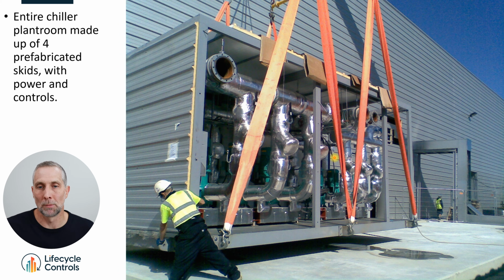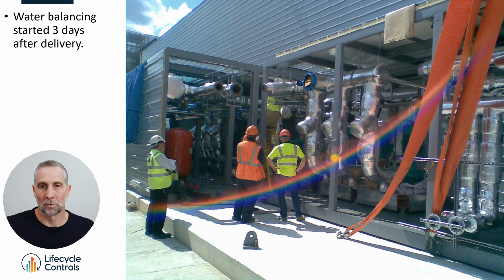This was a chiller plant room that was broken up into 4 separate skids. So it's 1, 2, this is the third piece. If I remember correctly, we designed the plant room for months and months and months, using 3D programs. I used to walk through the plant room and see where the pipes went and where I could put different things. Then they built these skids off-site at a factory, and they came on a truck. If I remember correctly, 3 days after these skids were delivered, the pipework was all flanged up, a roof was put on top, and the main power feed came on, we started water balancing. 3 days after these things were delivered to site.